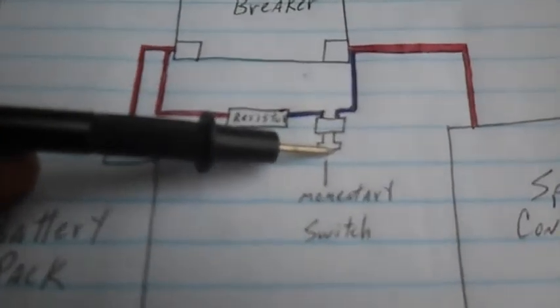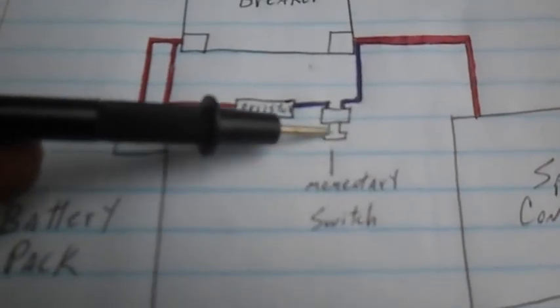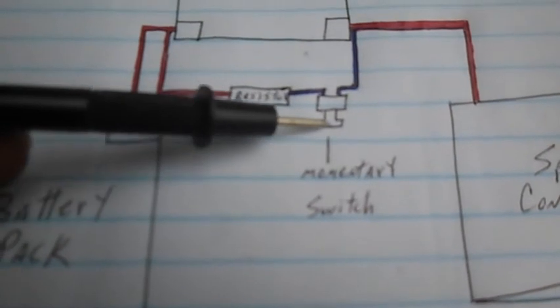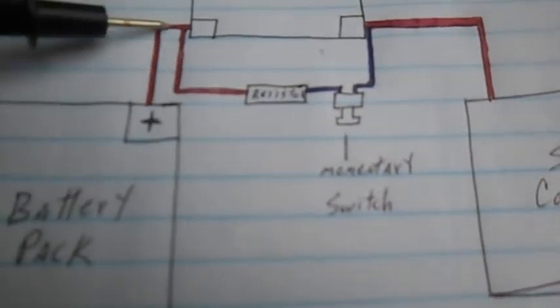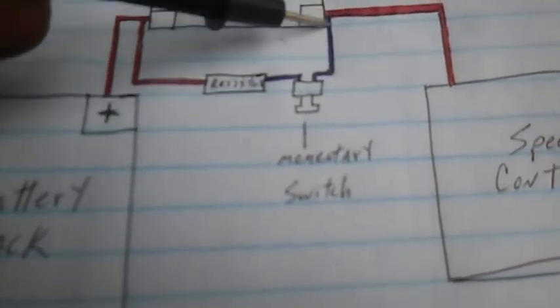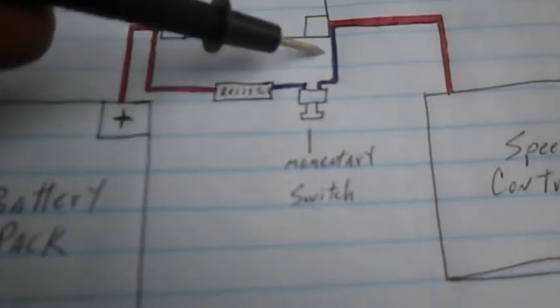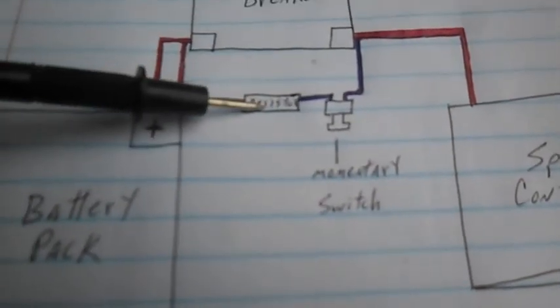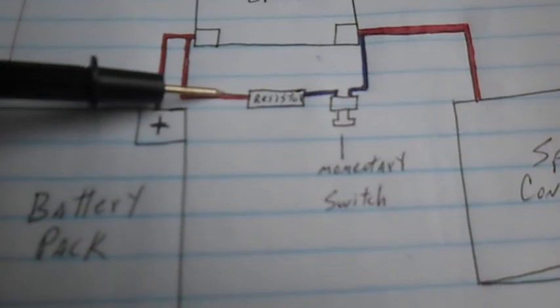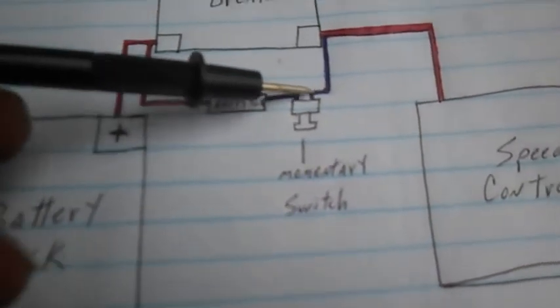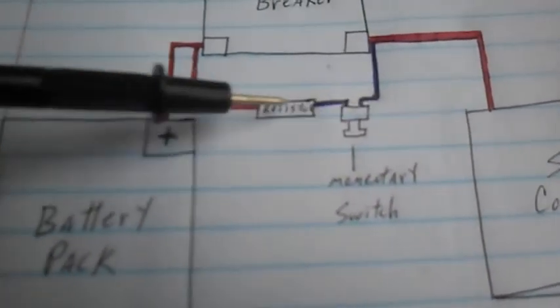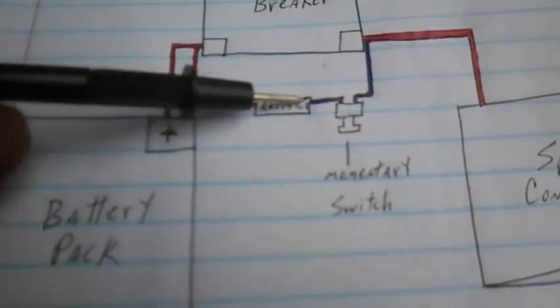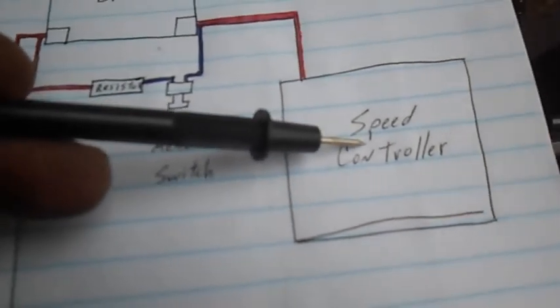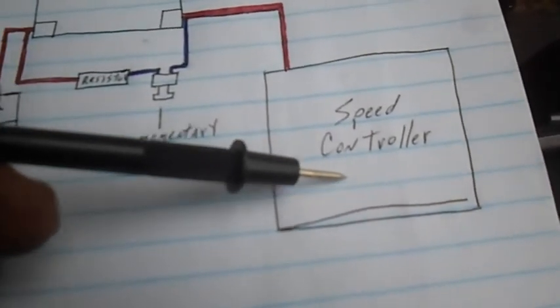The battery is separated from the whole rest of the system. But if and when you push this momentary push button switch, it connects this jumper circuit, bypassing the circuit breaker through a resistor, and lets just a small amount of voltage across at a time. This way we slowly fill up the capacitors in the speed controller.